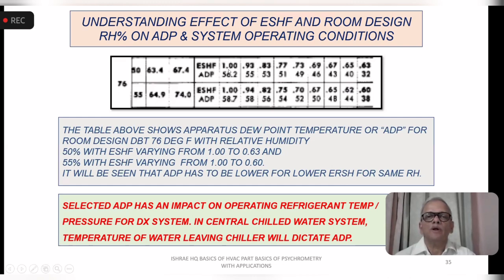1, 0.93, 0.83, 0.77, 0.73. So these are the values of the effective sensible heat factor, and for 55% also in a similar way. The above table is showing the apparatus dew point temperatures, or ADP, for the room design of 76 with relative humidity 50% and 55%. And these are the values. Now you will see that the ADP temperature is lower as the sensible heat factor is reducing.